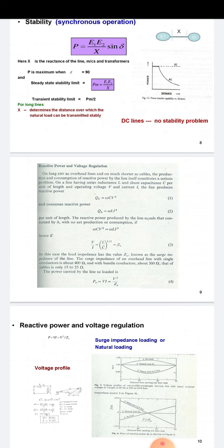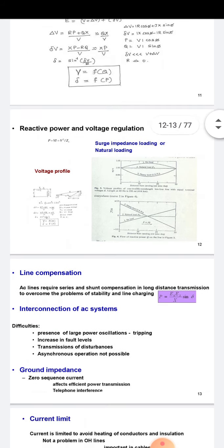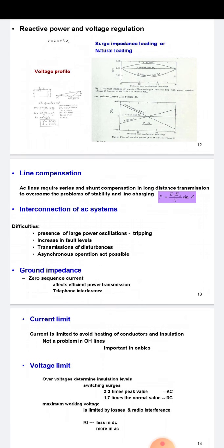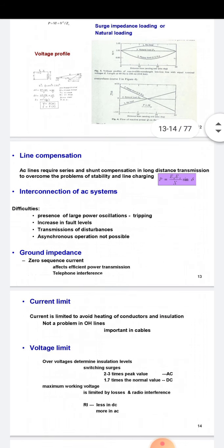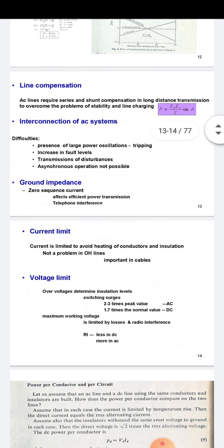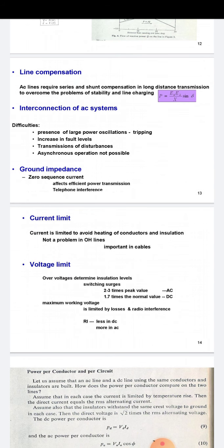Line compensation: AC lines require shunt and series compensation in long-distance transmission to overcome line charging and stability limitations. Series capacitors and shunt inductors are used for this purpose. Increased power transfer and voltage control are also possible through static VAR systems (SVS). Interconnection of AC systems has difficulties including large power oscillations, increased fault level, transmission of disturbances, and that synchronous operation is not always possible.